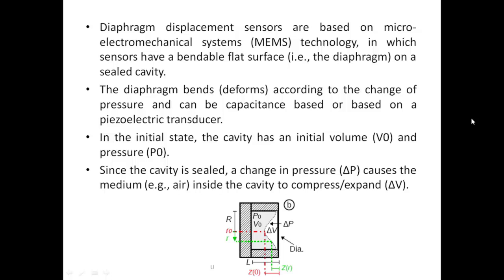The second important fundamental is diaphragm displacement sensors. This is very important when it comes to measuring internal pressures. If for any particular reason you have to implant a pressure sensor inside, if you have to make a cut in the skin and plant a sensor inside, we usually use diaphragm displacement sensors.